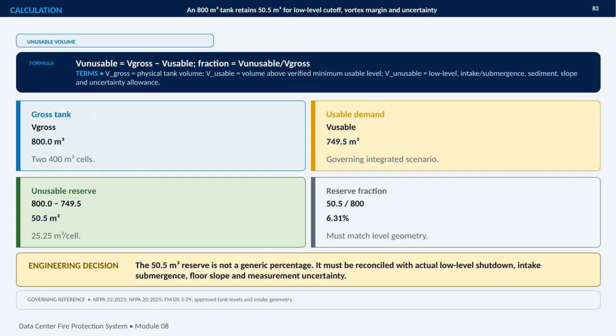flow requirements. This slide calculates the tank volume that cannot be counted on for fire protection demand. The gross tank volume is 800 cubic meters, arranged as two 400 cubic meter cells. After accounting for the governing integrated scenario, the verified usable volume is 749.5 cubic meters. The difference is the unusable reserve, 800 minus 749.5, which equals 50.5 cubic meters, or 25.25 cubic meters per cell. Expressed as a fraction of the total tank, that reserve is 50.5 divided by 800, or 6.31%.